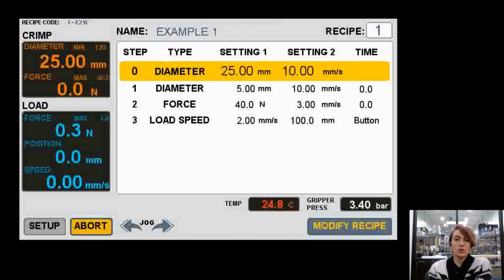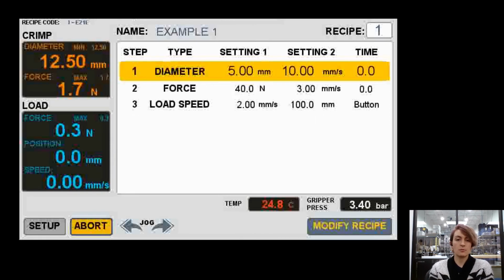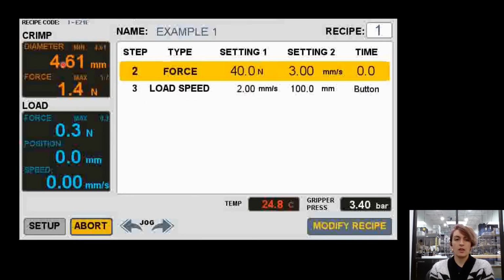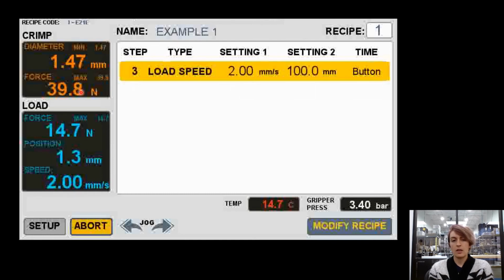Now you can just push the green start button on the machine to get the recipe started. First, we're doing a 5 millimeter diameter step. Then it moves on to a second step. So the machine is slowly reducing its size until it starts to crimp on the stent. Then we'll see the force jump up. Once it hits 40 newtons, it moves on to the load speed step.